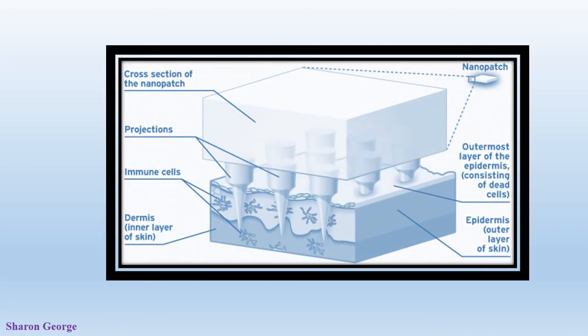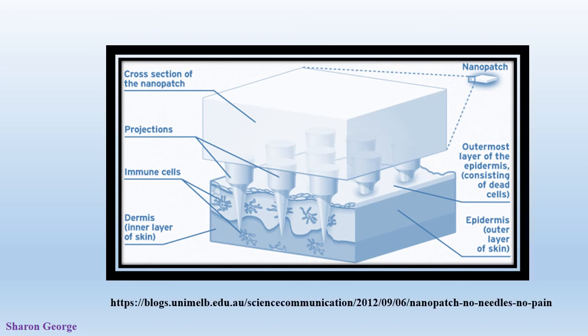In this picture we can see the Nanopatch structure. Many projections are visible. The Nanopatch is made with a tiny piece of silicon covered on one side with up to 20,000 microscopic projections per square centimeter. Each of these projections is coated in a dry vaccine, and when the patch is applied, the projections deliver the vaccine just below the top layer of the skin, which is abundant in immune cells. Within a minute, the vaccine becomes wet in the cellular environment and is released.